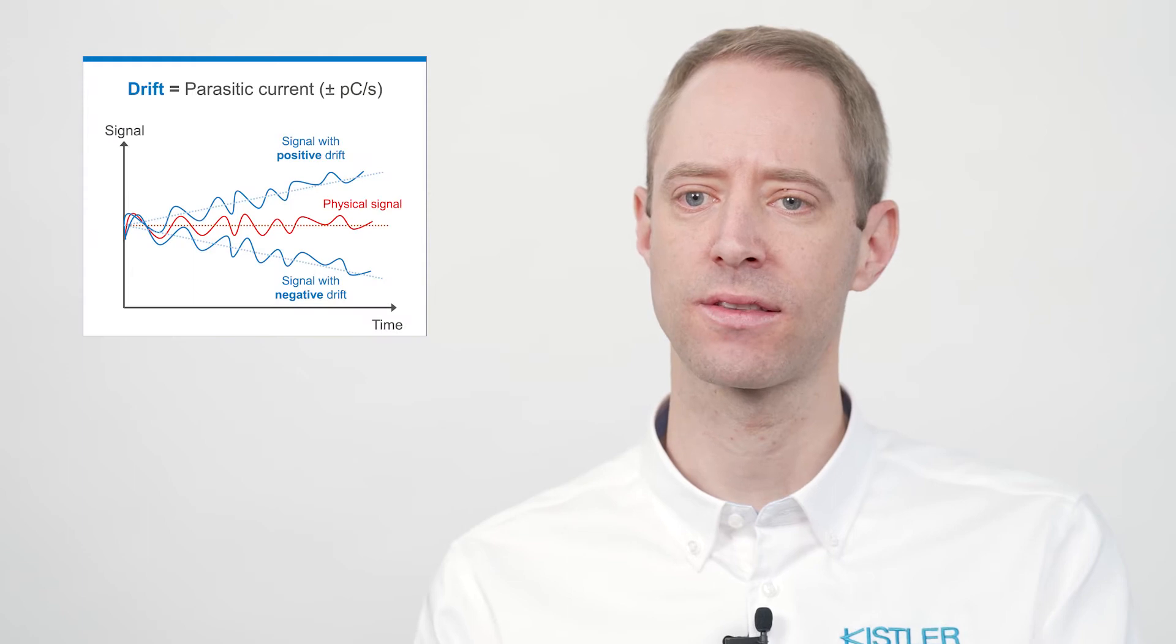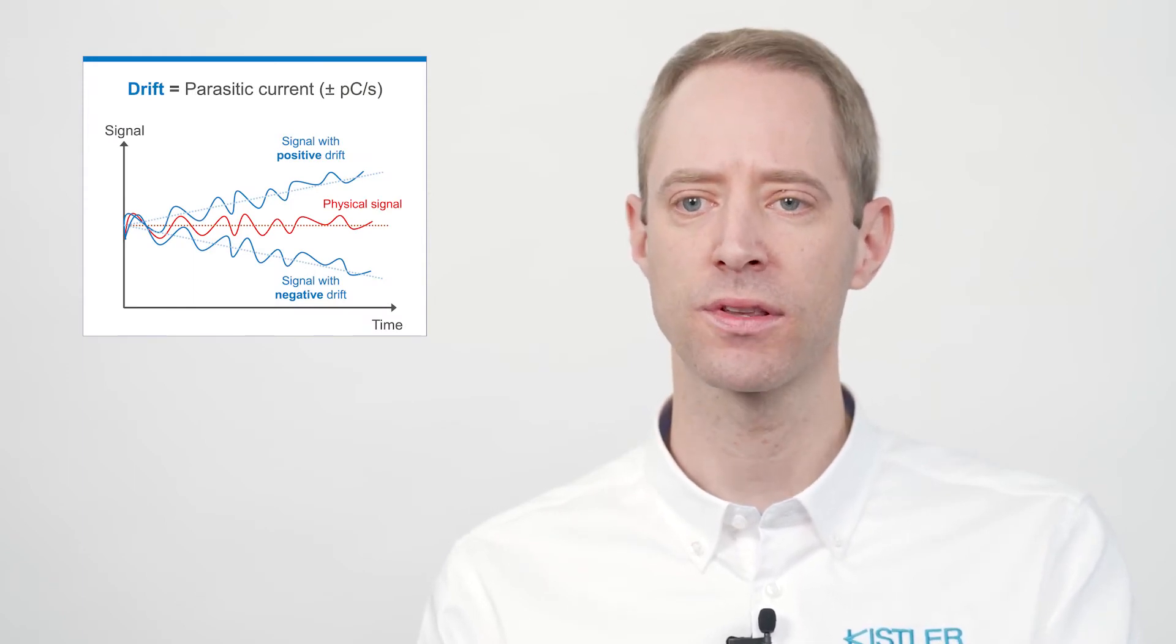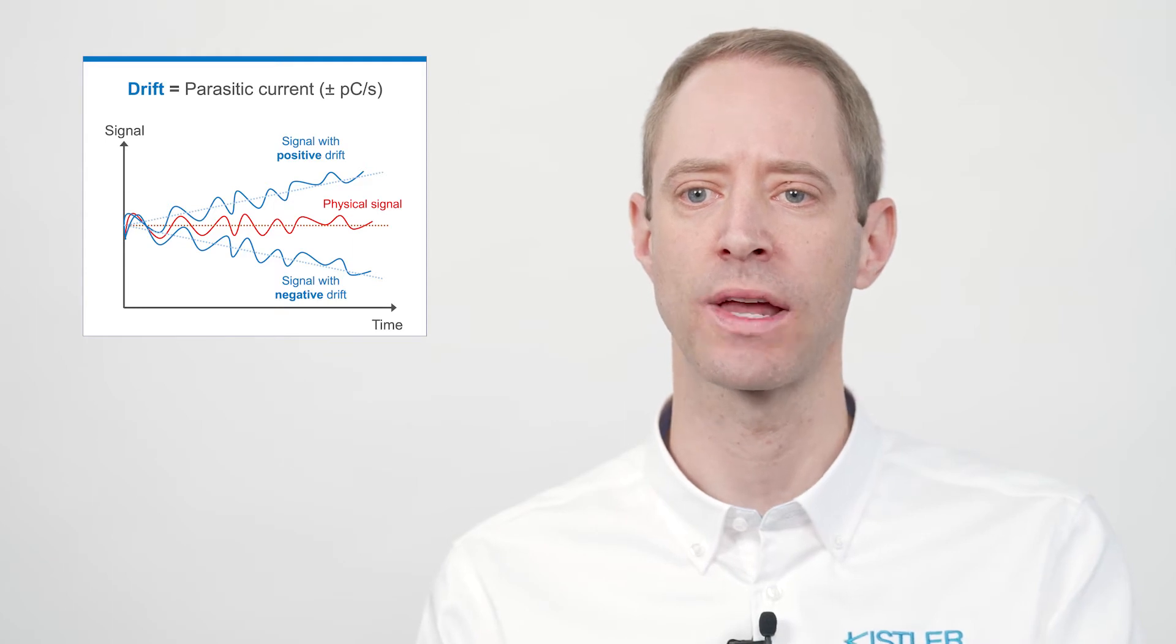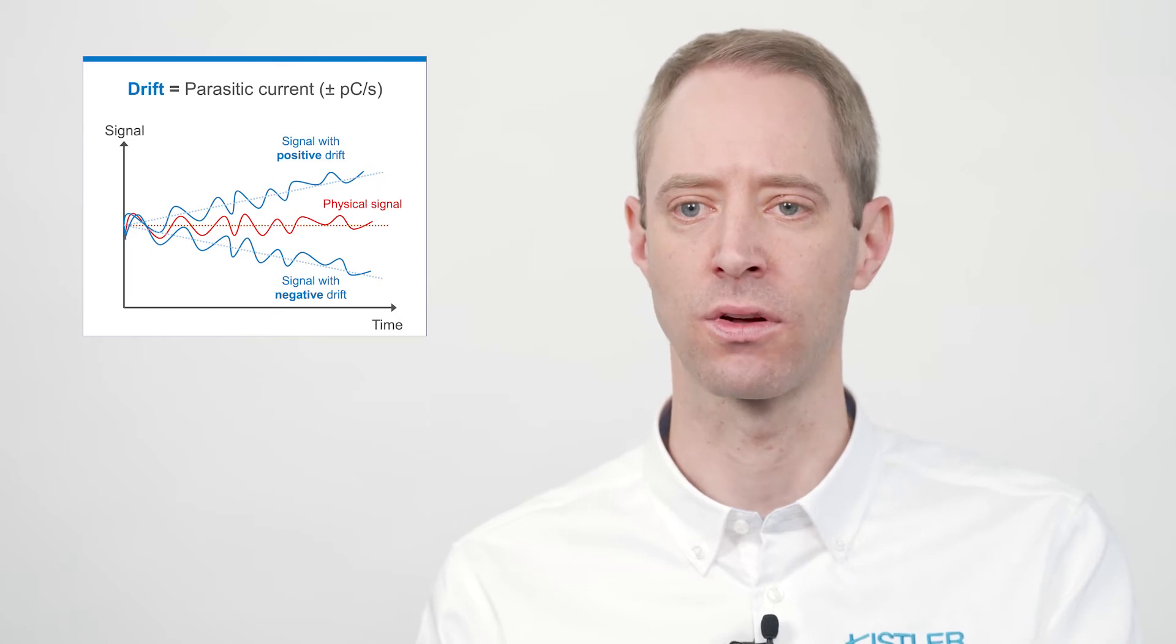So far so good, but what is actually a drift in a piezoelectric measuring chain? A drift is a parasitic current and is expressed in picocoulombs per second. Both negative and positive drifts can occur in a piezoelectric measuring chain. In this video, I'm going to focus on linear drifts only.